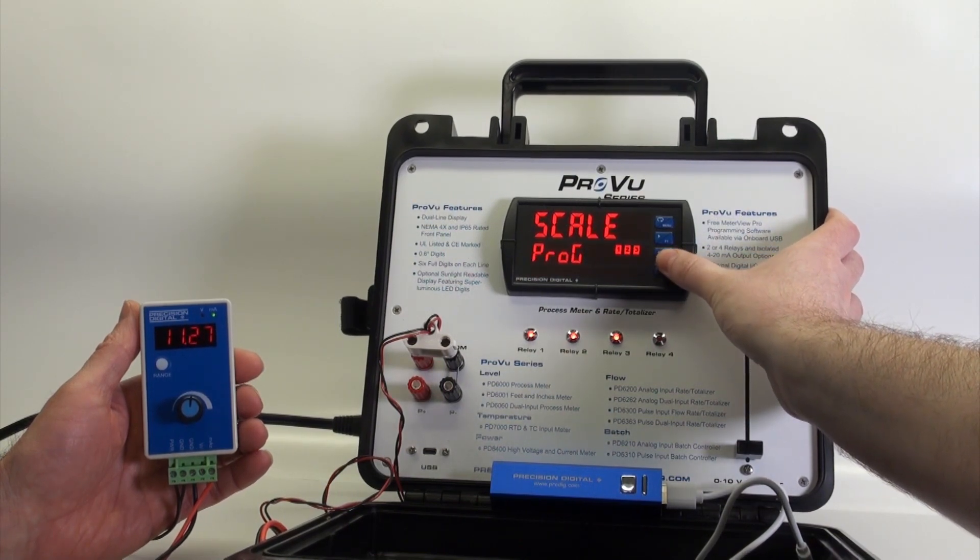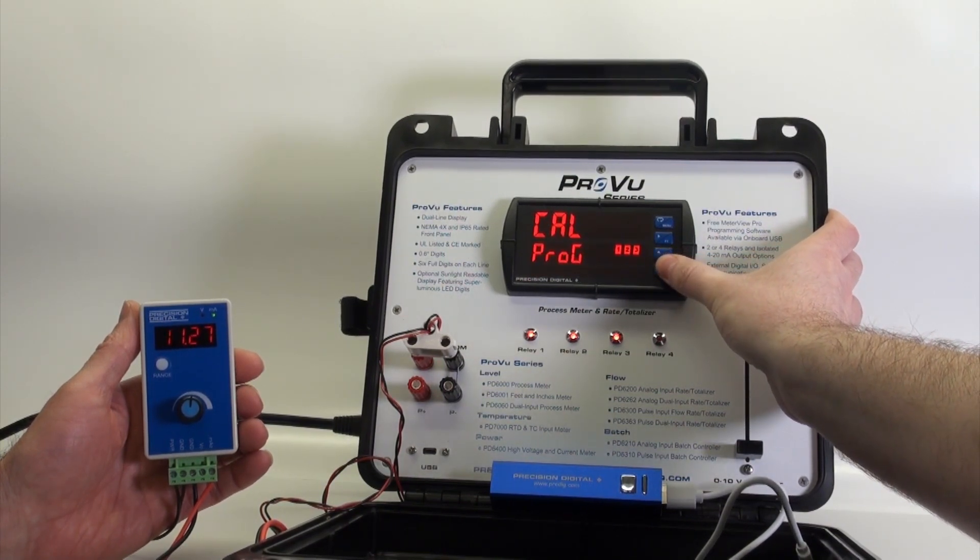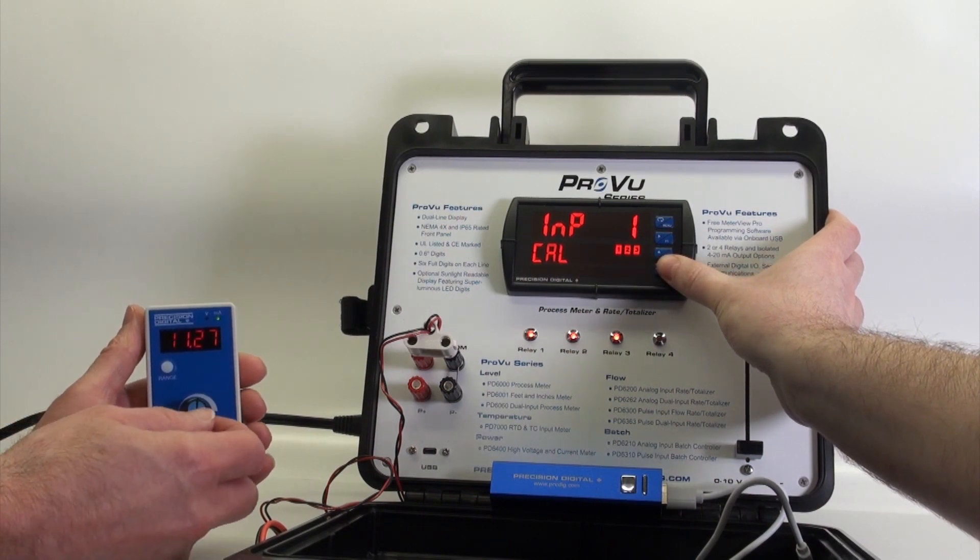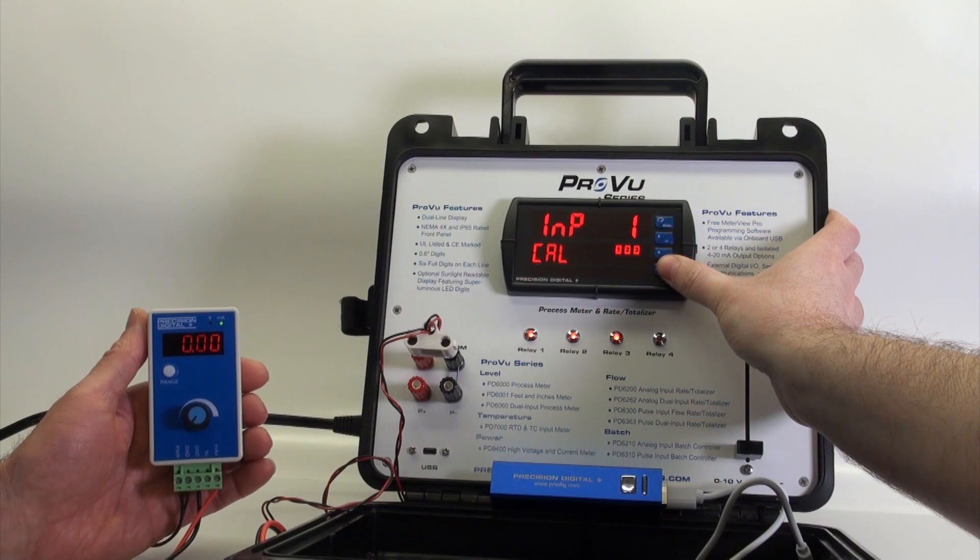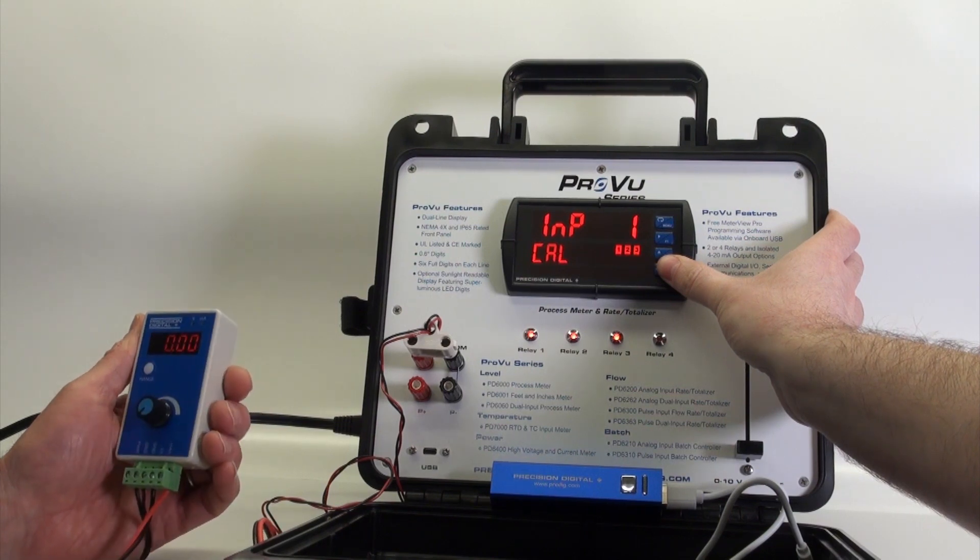We'll go to the internal calibration feature, and now the meter is asking us for input one, so all we have to do is dial the pot down to 4 milliamps.